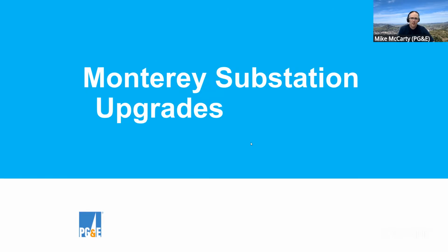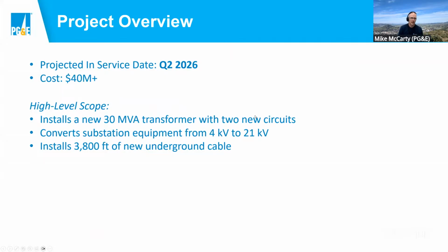So going into what it is we're doing here. We are getting pretty close to wrapping up this project. We have a projected in-service date of Q2. So only here in a few months, we plan on going operational with what will ultimately be an over $40 million project to upgrade the substation and the surrounding areas. At the core of this project, it was installing a 30 MVA transformer and 2 new feeders. But to accomplish this, the scope of the project more closely resembles a substation rebuild because we actually were converting the voltage that this substation serves. Historically, it was serving primarily 4 kV, and we're actually upgrading it to 21 kV.